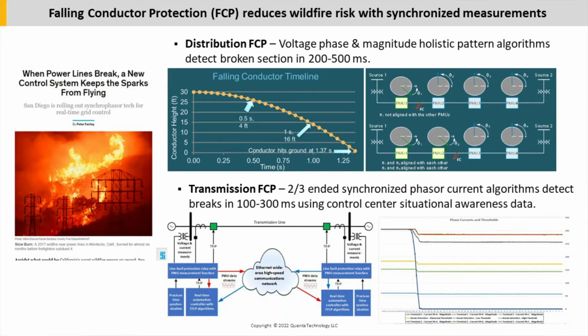Reduction of fire risk is a top priority, so we focused on development of a system that detects and trips when a broken conductor has fallen only a few feet. This avoids an arcing ground fault that we could not otherwise detect.